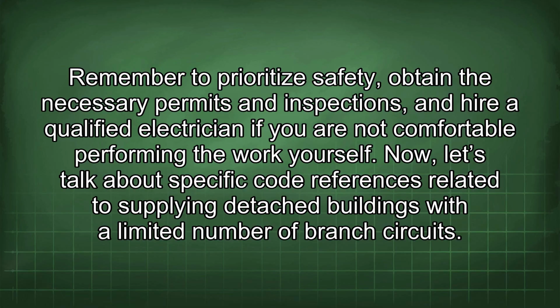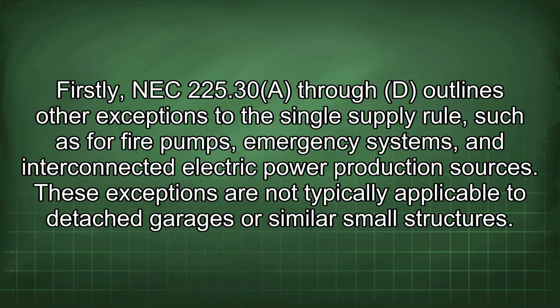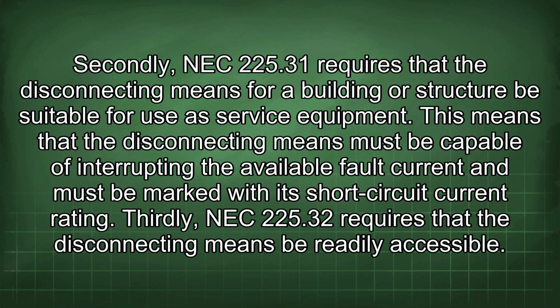Firstly, NEC 225.30(A) through (D) outlines other exceptions to the single supply rule, such as for fire pumps, emergency systems, and interconnected electric power production sources. These exceptions are not typically applicable to detached garages or similar small structures. Secondly, NEC 225.31 requires that the disconnecting means for a building or structure be suitable for use as service equipment. This means that the disconnecting means must be capable of interrupting the available fault current and must be marked with its short circuit current rating.